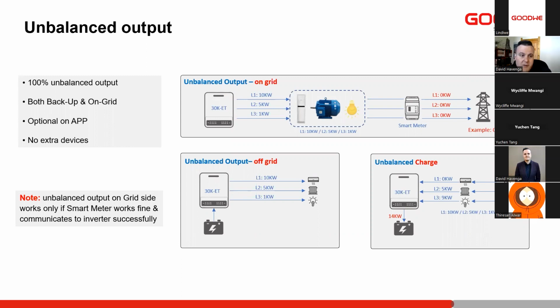You're still consuming quite a bit of energy from the grid, and any small loads like that we won't be able to cover. But with the unbalanced output on our ET devices, it's individual phase limits. So it will give you what you need per phase up to the maximum of the inverter's per phase output. Always keep in mind the 3-phase inverters, you'll have your 30 kilowatt divided by 3, so it means 10 kilowatt per phase maximum in output. So if your loads are like this, 10, 5, and 1, the inverter will produce that and ensure zero export on each phase. So it will give you a great advantage in the savings compared to your conventional zero export. Because with conventional export, your inverter would actually be producing only 3 kilowatt because your lowest phase is 1 kilowatt. It produces 1 kilowatt on each phase.